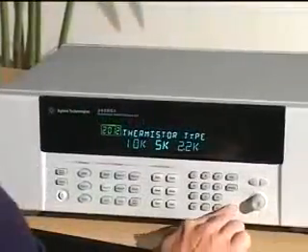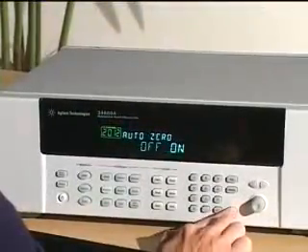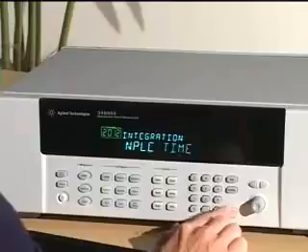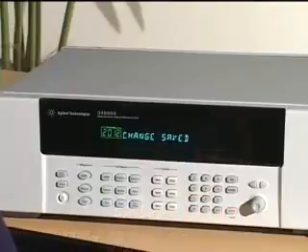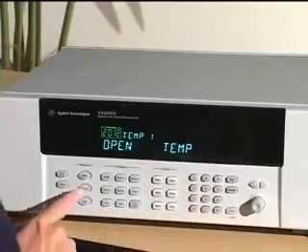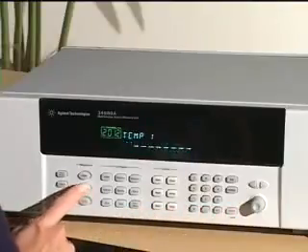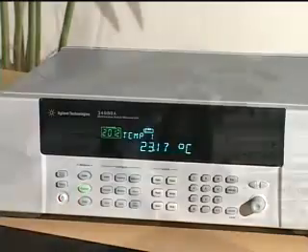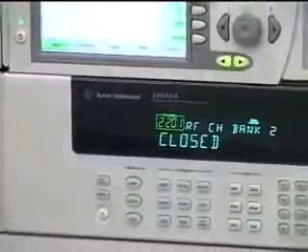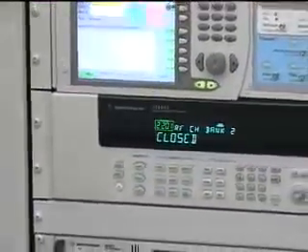Additionally, the 34980A offers more channels, a larger switch matrix, faster reading rates up to 1,000 measurements per second, and a wider variety of modules. The 34980A is ideal for medium to large systems and provides a low cost alternative to VXI or PXI.